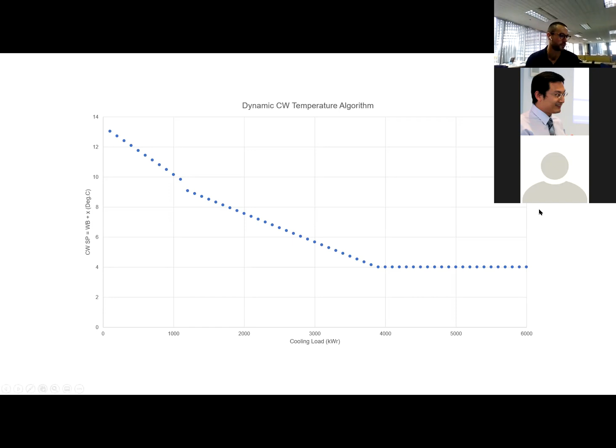The last recommendation in this case was the load balancing, and this is just an excerpt from the report that explains what we're trying to achieve with load balancing. To summarize what's on this slide, load balancing is when we've got 2 differently sized chillers running simultaneously. So this would be in stage 3 with that low load and high load chiller both running. And in this case, what the model suggests is that we should restrict or demand limit one of these 2 chillers so that each of them is operating within their optimal part of that part load efficiency curve. And what that looks like practically is this here.